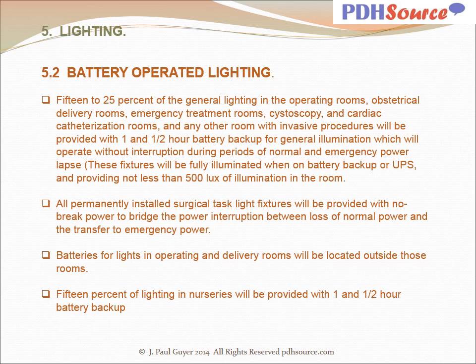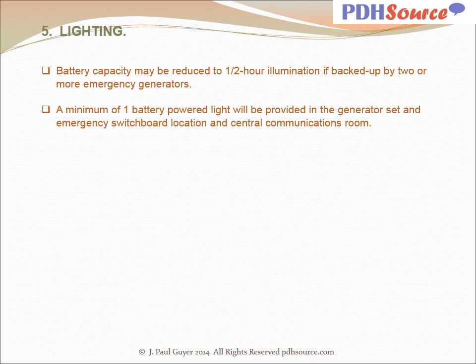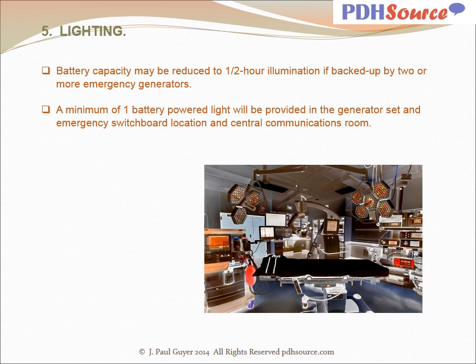Fifteen percent of lighting in nurseries will be provided with 1.5 hour battery backup. Battery capacity may be reduced to 0.5 hour illumination if backed up by two or more emergency generators. A minimum of one battery powered light will be provided in the generator set, an emergency switchboard location, and central communications room.